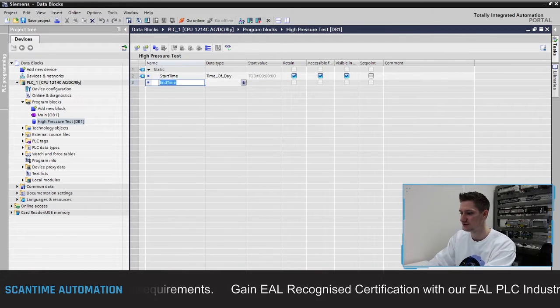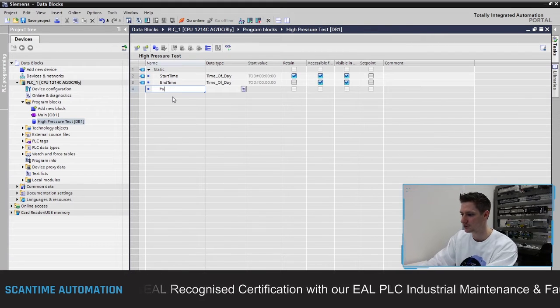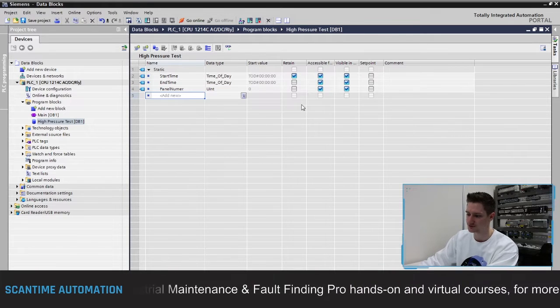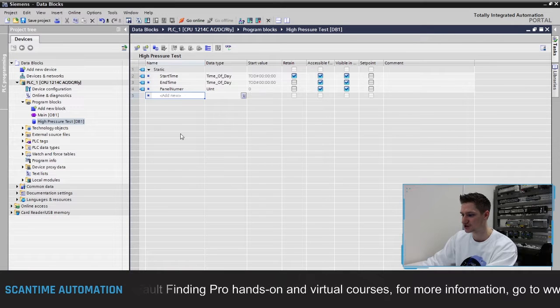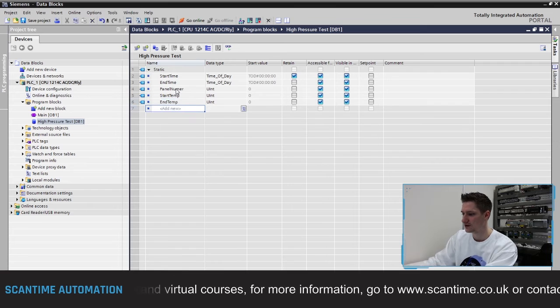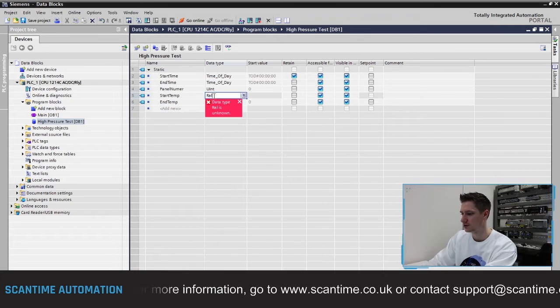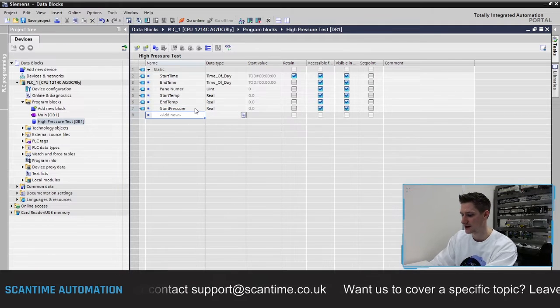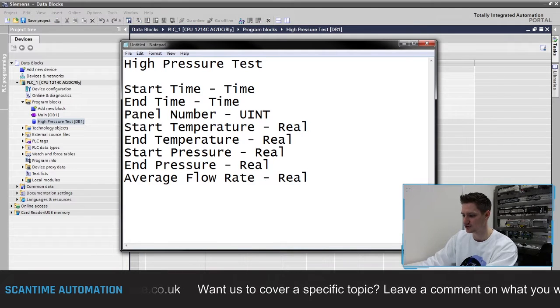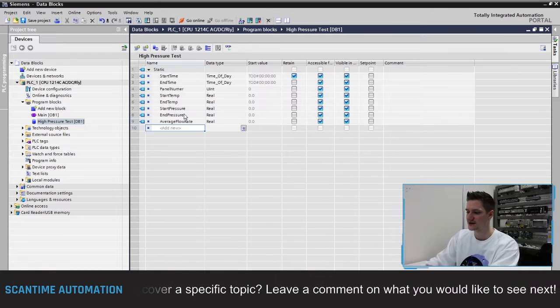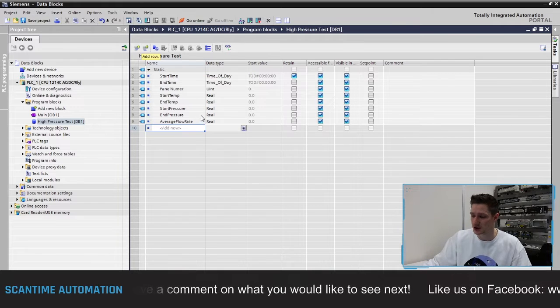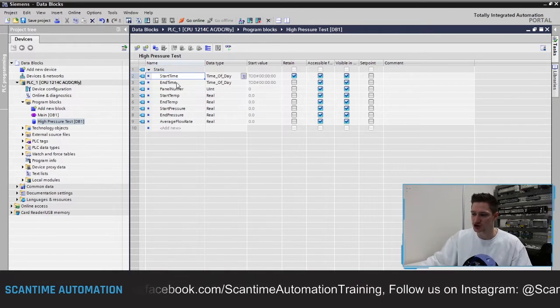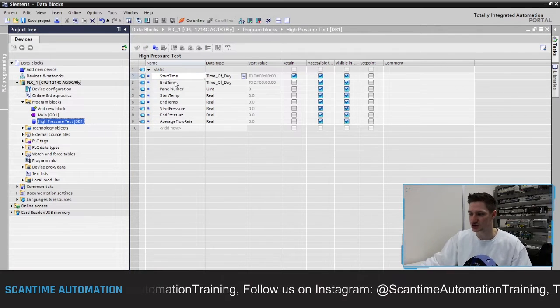We'll then add 'end_time' also as Time of Day, 'panel_number' as an unsigned integer — meaning completely positive values — and then 'start_temperature' and 'end_temperature' as real values. We'll also add 'start_pressure', 'end_pressure', and 'average_flow_rate'. All I'm doing is filling this data block with names for the data we want to store. The PLC is now assigning a part of its memory to this High Pressure Data Block DB1 and storing a part of that for each named variable.